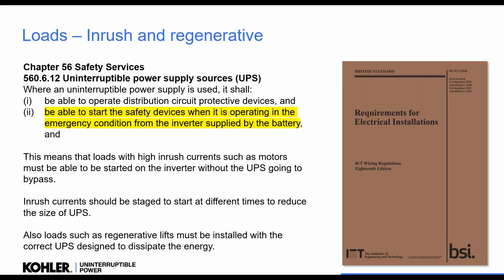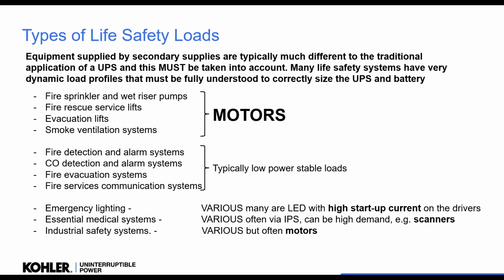Understand what type of lift we have, because it could be regenerative. Any of the loads we have, sprinkler pumps, riser pumps, lifts, smoke extract, they're all motors. And if they're not turned on carefully, we're going to get high startup currents from these motors, which we have to be very wary of. There's a lot of low power stable loads, that's fine, no problem. And this is just easy to calculate, we know the load.